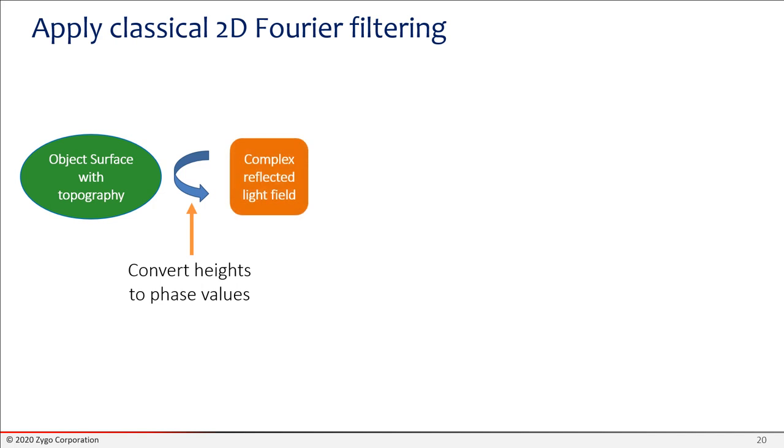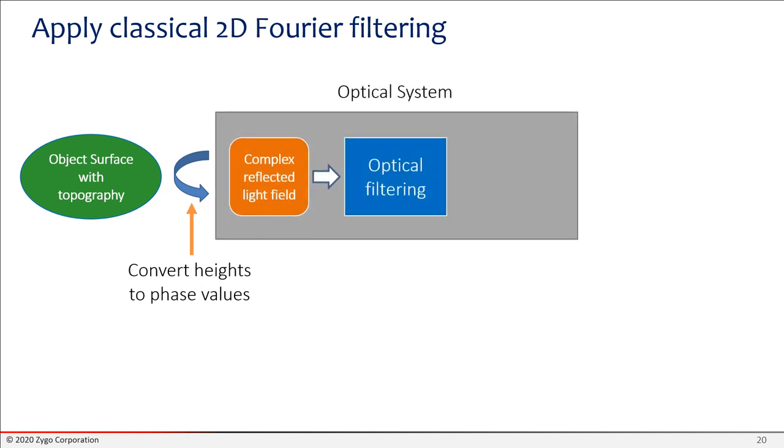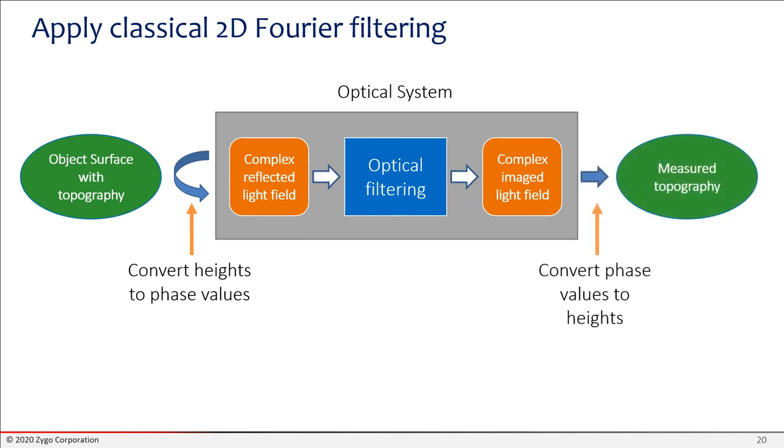Now of course in an optical system we usually use lenses and mirrors and so forth to create the far field without going off to infinity, but that's the basic idea. The next step is where our Fourier optics comes in. We're going to take our part, shine light on it, and that will give us a complex reflected field. And then we're going to feed that into an optical system. And that optical system is going to apply some optical filtering that might attenuate or even distort the signal somewhat. Once that's done, we're going to look at the complex image light field that comes out the other side. To get the surface topography, we have to interpret the phase values of that complex image light field, and that gives us the measured topography. So a lot of what's important in this model is how the optical filtering takes place.